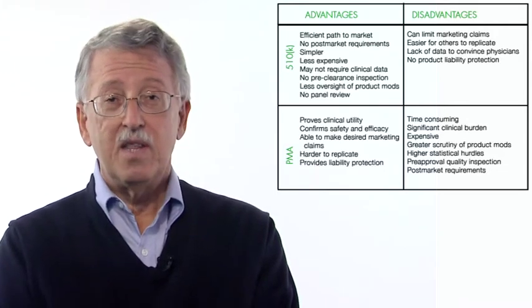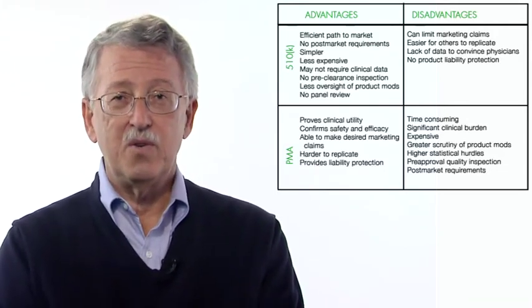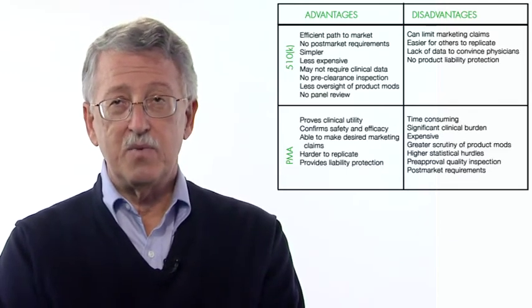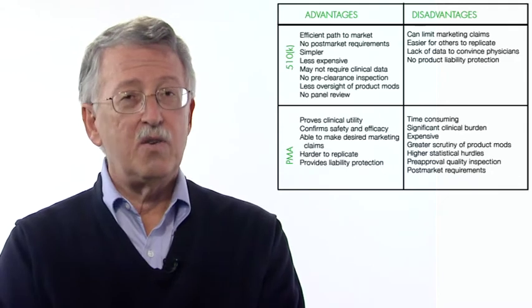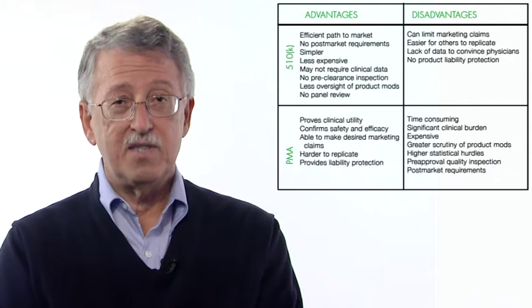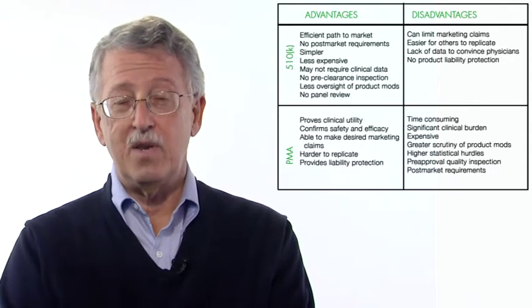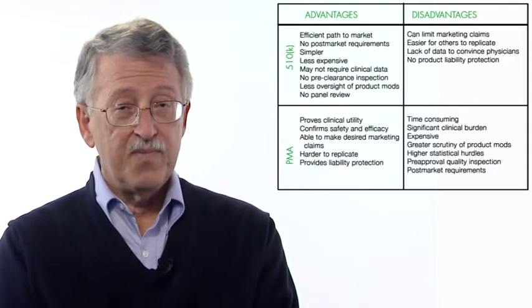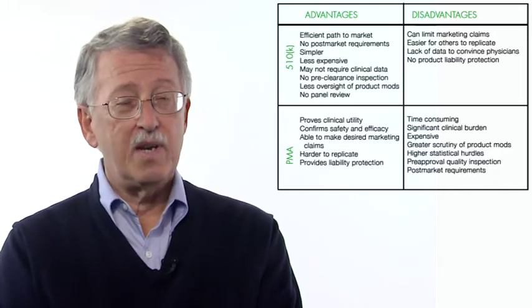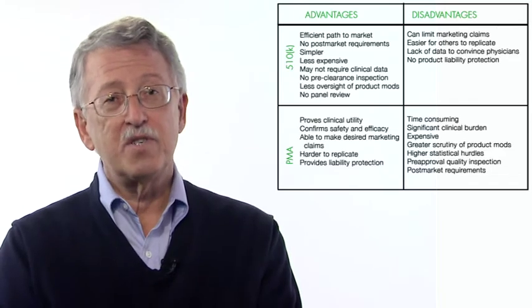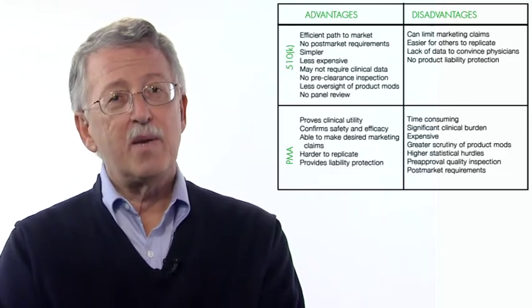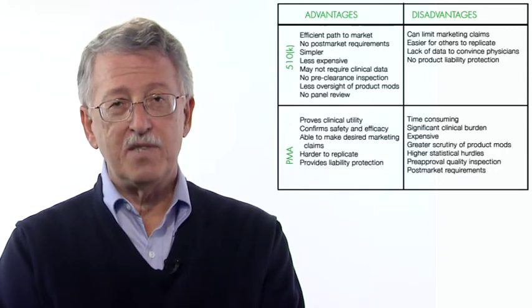With respect to PMAs, the pros for a PMA include the fact that you're proving clinical utility and outcomes, which is something that the user community and clinician community would like to see. And FDA is making a finding that the product is safe and effective, and you can make that claim in your marketing materials. In effect, the PMA is a regulatory license, so it's harder for other companies to come along and copy or submit a Me Too version of your product. And the Supreme Court has created product liability protection for devices that have gone through the PMA process.